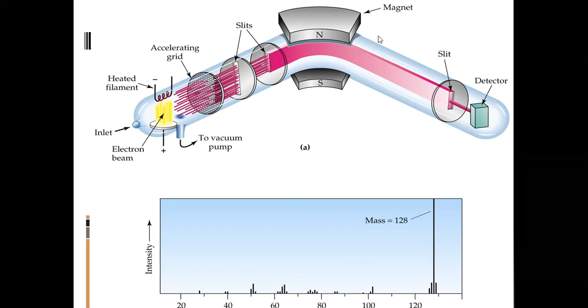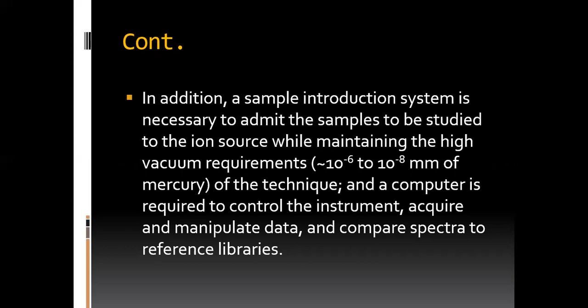In addition, a sample introduction system is necessary to admit the samples to be studied to the ion source while maintaining the high vacuum requirements, which is approximately 10^-6 to 10^-8 millimeter of mercury. And a computer is required to control the instrument, acquire and manipulate data, and compare spectra to reference libraries.